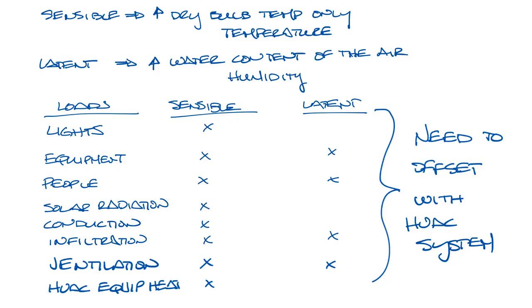Let's make a little more room now. To know how much capacity your HVAC system needs to have, you need to know the load of the building and the load equation. So the load equation is Q equals 1.08 times CFM times delta T.